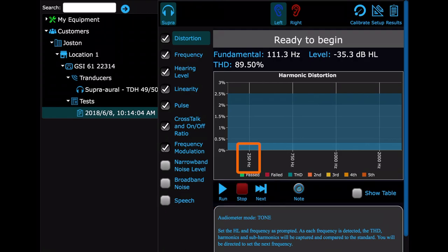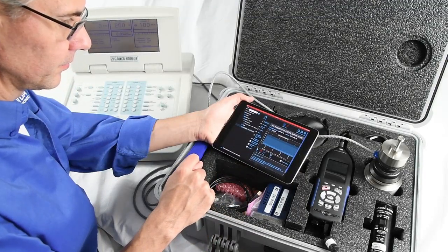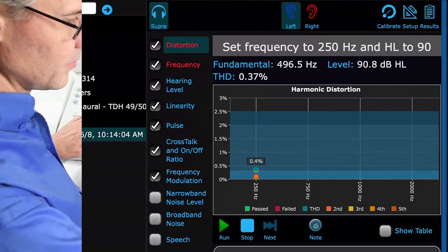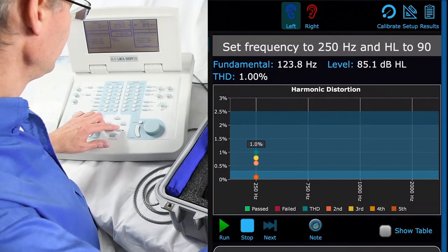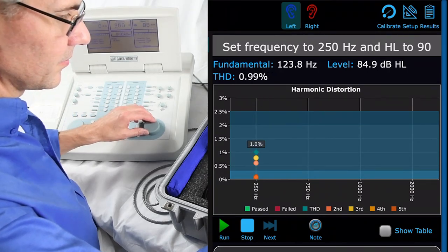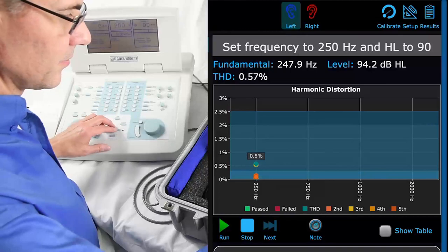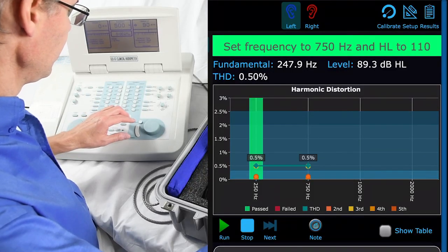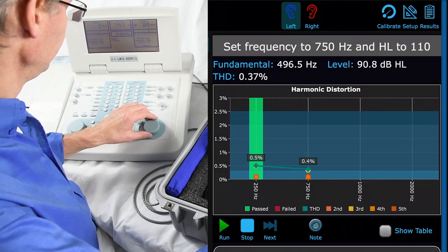We know the distortion test will first look for 250 Hz frequency, so we set the audiometer to 250 Hz and then begin. AudCal will automatically detect the conditions of the test, then move on to the next step. As the technician, you only have to follow the instructions in the top gray bar to advance to the next step.